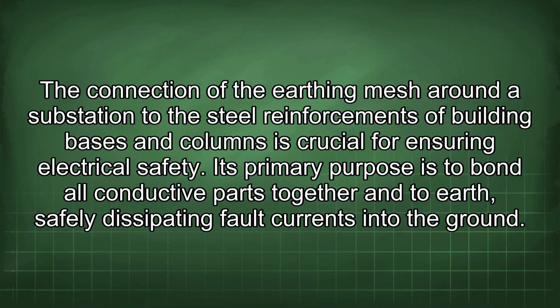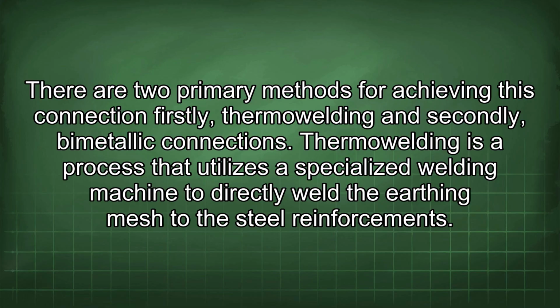The connection of the earthing mesh around the substation to the steel reinforcements of building bases and columns is crucial for ensuring electrical safety. Its primary purpose is to bond all conductive parts together and to earth, safely dissipating fault currents into the ground. There are two primary methods for achieving this connection: firstly, thermowelding, and secondly, bimetallic connections.